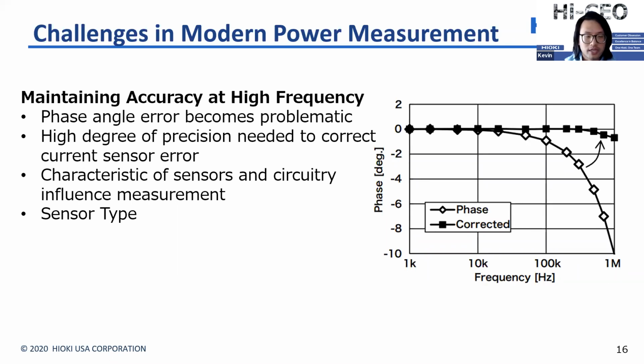On the other hand, we also have the clamp types, which have a break in their magnetic core, but this allows us to conveniently clamp onto wires we wish to measure. But because there's the break in that core, it's a little bit more difficult to obtain that uniform characteristic. So the clamp type sensors will generally have less accuracy, and they will have a greater effect from the position of the wire than the through type sensors.